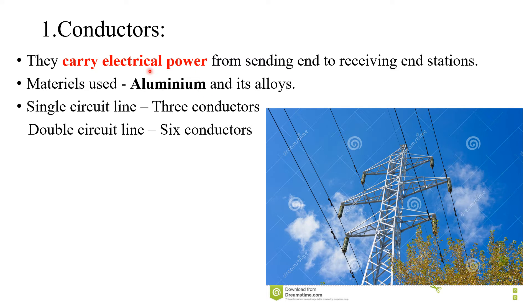First, we will discuss conductors or transmission lines. They carry electrical power from the sending end to the receiving end stations — they are the carriers of electrical power. The materials mainly used for conductors are aluminum and its alloys, because aluminum has good conductivity and its weight is very less compared to a good conductor like copper. For single circuit lines there will be three conductors and for double circuit lines there will be six conductors.